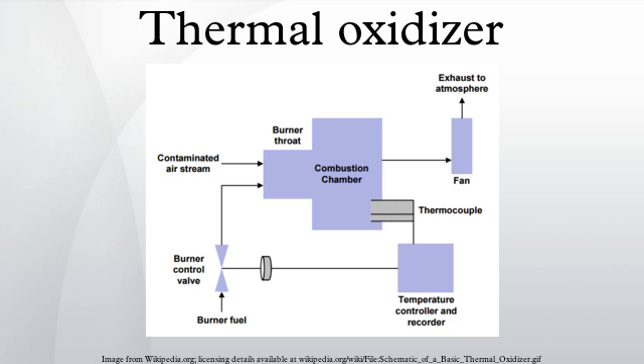Regenerative thermal oxidizers are ideal in a range of low to high VOC concentrations up to 10 grams per cubic meter solvent. There are currently many types of regenerative thermal oxidizer on the market with the capability of 99.5% volatile organic compound oxidation or destruction efficiency. The ceramic heat exchanger in the towers can be designed for thermal efficiencies as high as 97% plus.